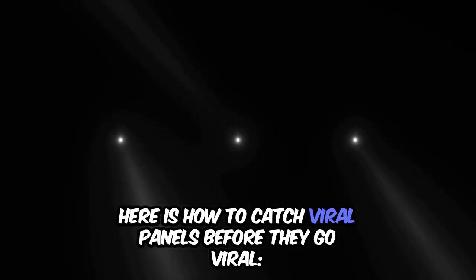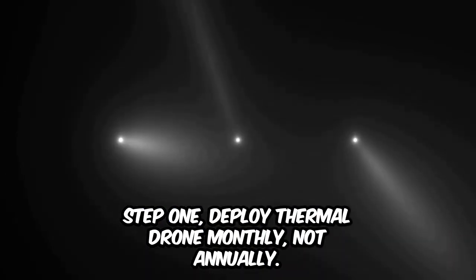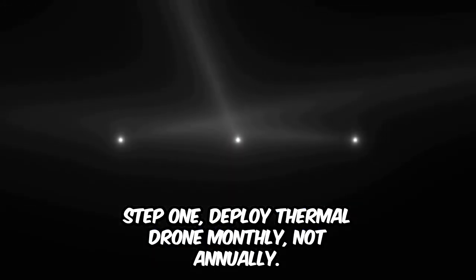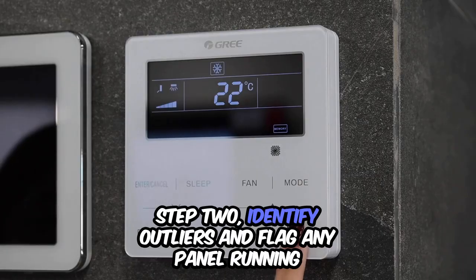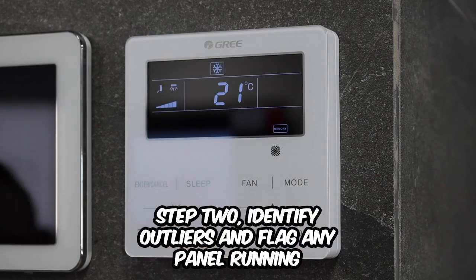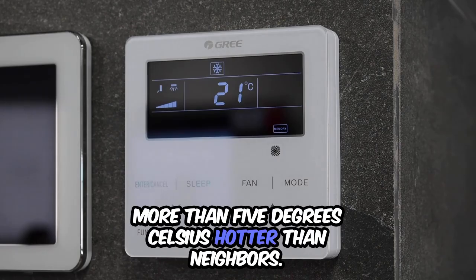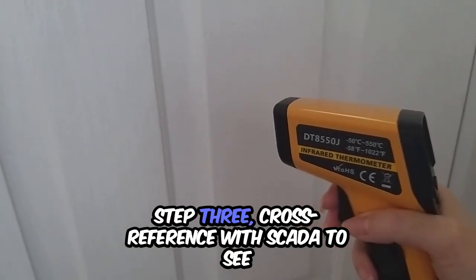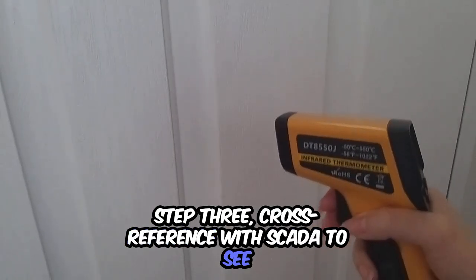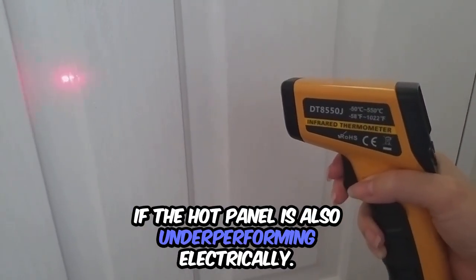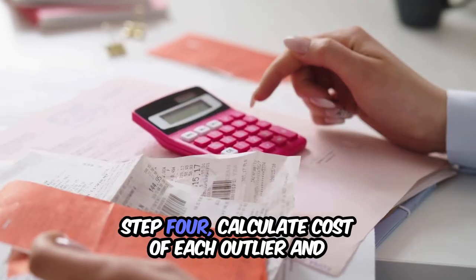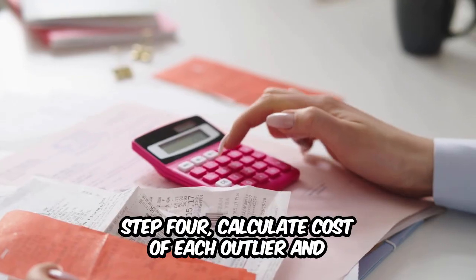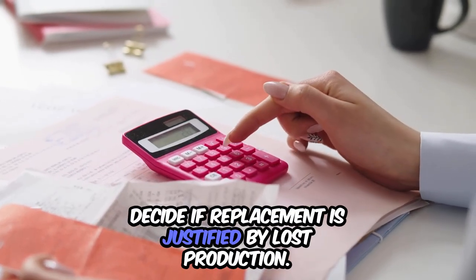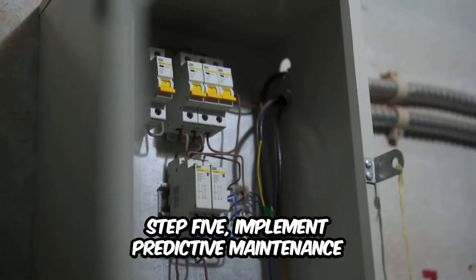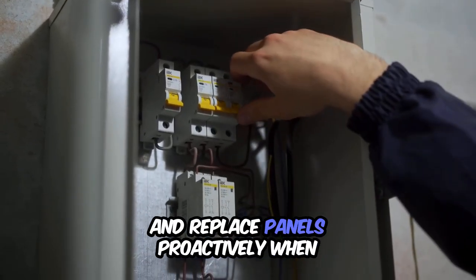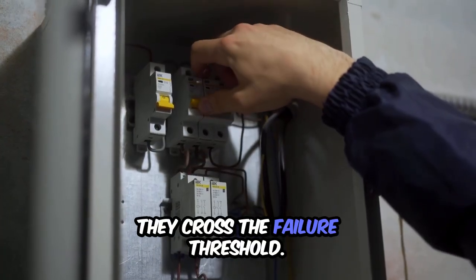Here's how to catch viral panels before they go viral. Step 1: deploy thermal drones monthly, not annually. Step 2: identify outliers and flag any panel running more than 5 degrees Celsius hotter than neighbors. Step 3: cross-reference with SCADA to see if the hot panel is also underperforming electrically. Step 4: calculate the cost of each outlier and decide if replacement is justified by lost production. Step 5: implement predictive maintenance and replace panels proactively when they cross the failure threshold.